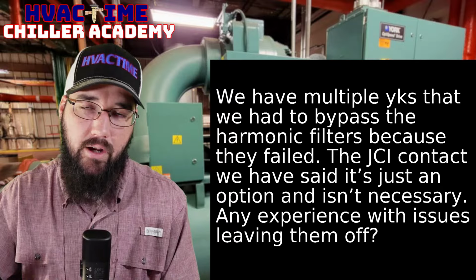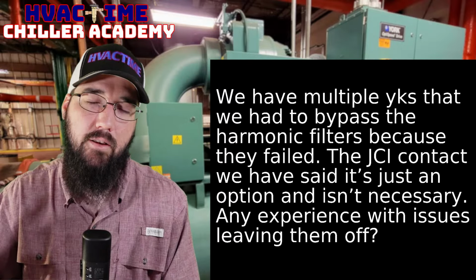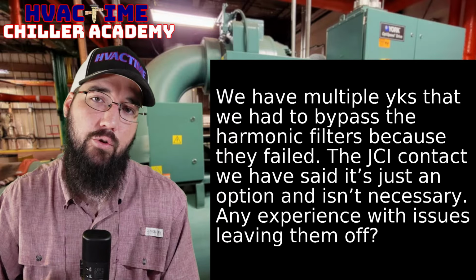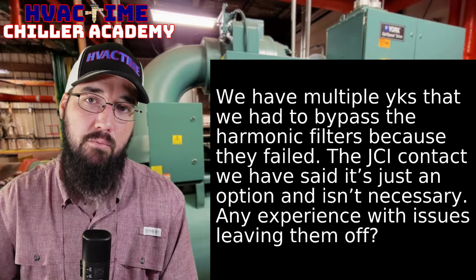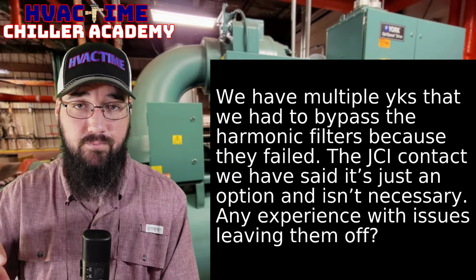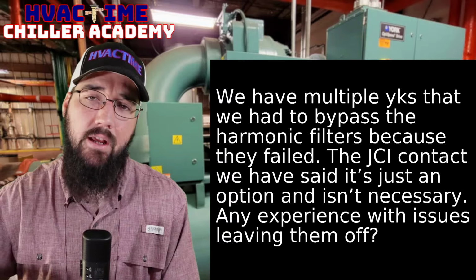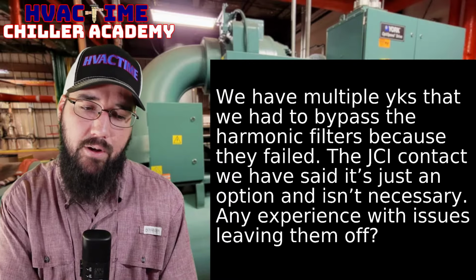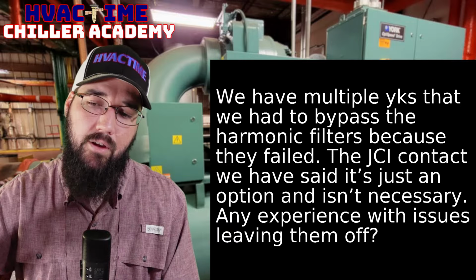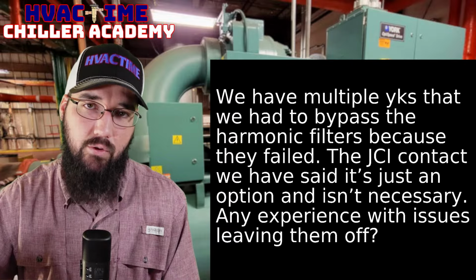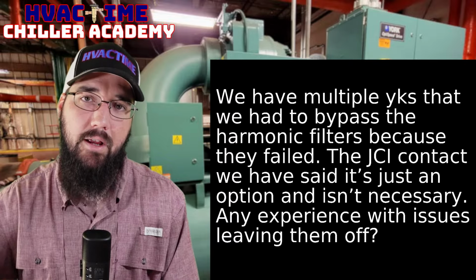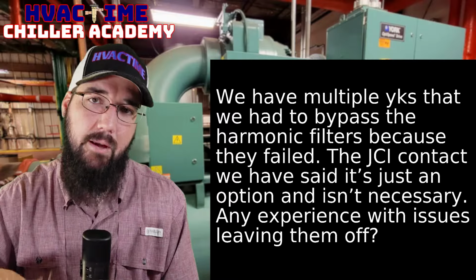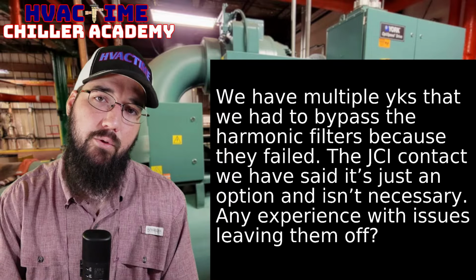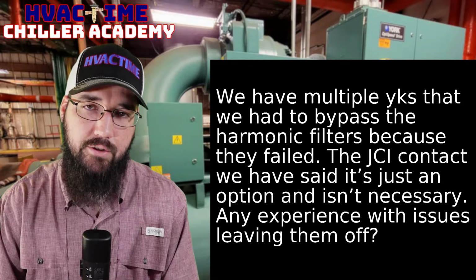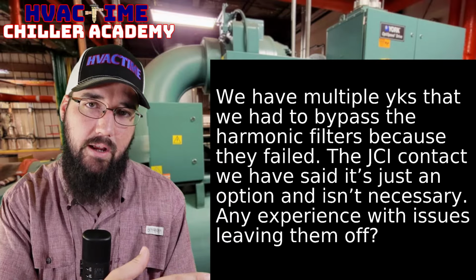As our drives become more advanced, we're starting to use IGBTs more and more for rectification coming in from the grid. So keep in mind, our drive assembly is bringing AC in. We then convert that to a DC voltage feeding into a capacitor bank, then reconvert that back into an AC through a set of inverters, which are IGBTs, leaving the drive assembly.